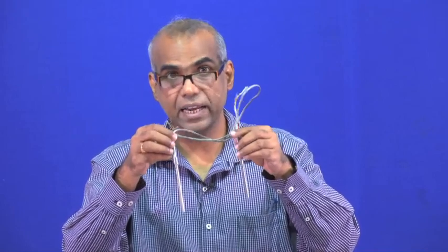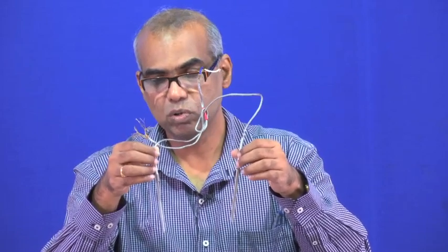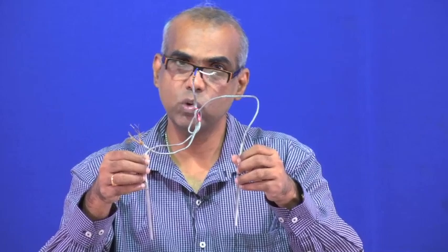First it was the thermocouple. This thermocouple is actually a K-type thermocouple, and you know the K-type thermocouple is a chromel alumel thermocouple. You have a chromel metal and an alumel metal, and you have made 2 junctions.